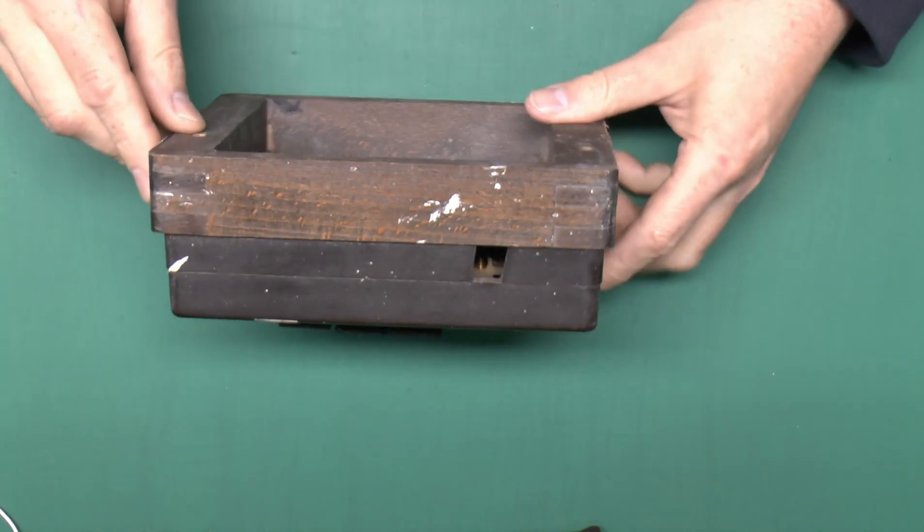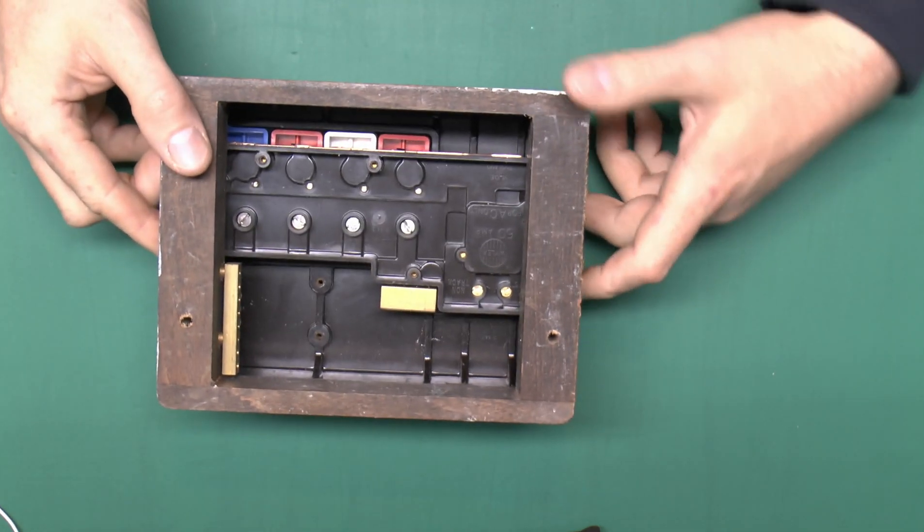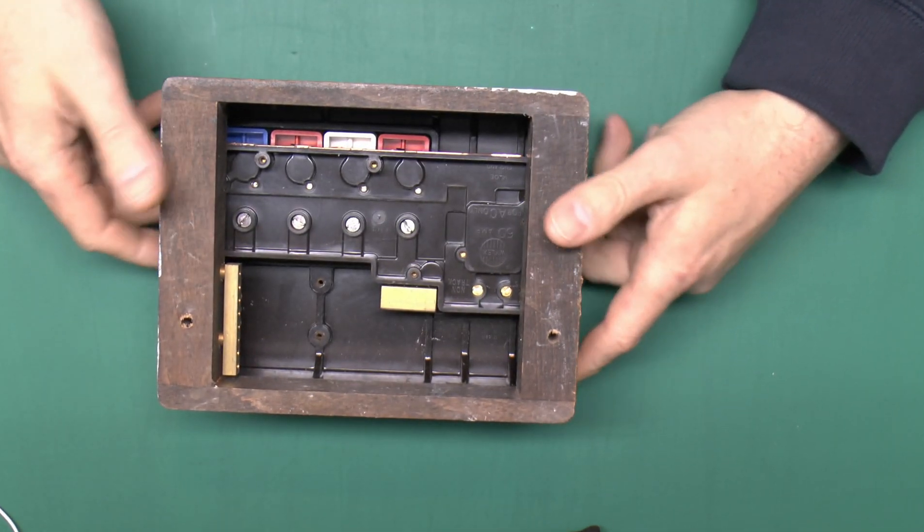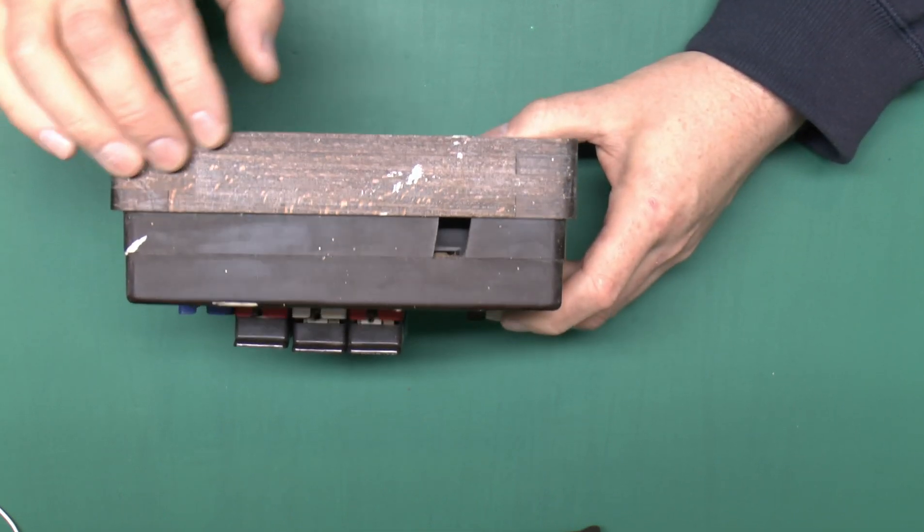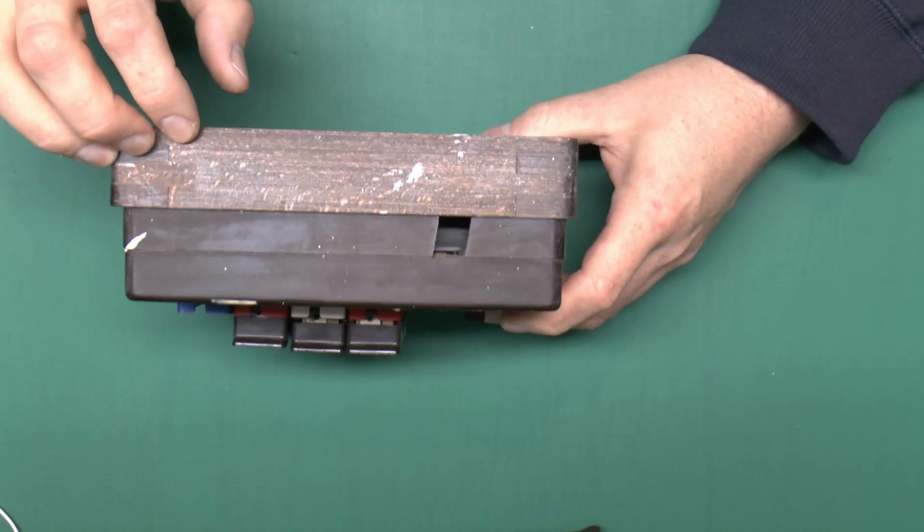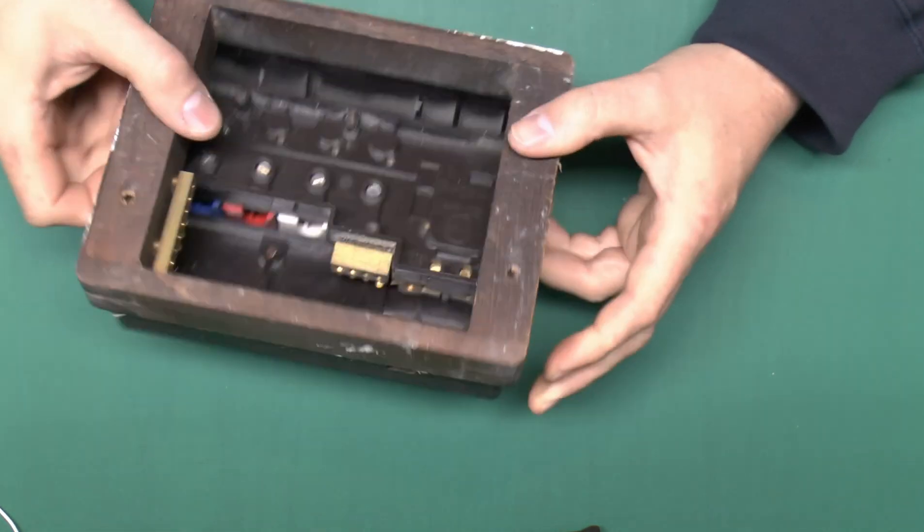The other problem with these ones is they have this wooden backing which though is allowed at the moment. That's when this is being recorded which is April 2014. Unfortunately, assuming the new regulations come out next year as they are currently described, this will no longer be permitted as it's a combustible covering.